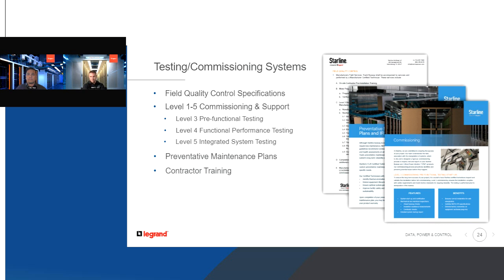Level 5, integrated system testing, is the same way. We can't stress that enough. You want a commissioning manager on site going through that level 5 plan, agreed upon between you, the commissioning agent, and your other vendors, on how you want to test the building. Because at the end of the day, we want to stay up and running and not have to shut those systems down for the next 7 to 10 years or so. You really want to make sure you're testing those systems to their max capacity.